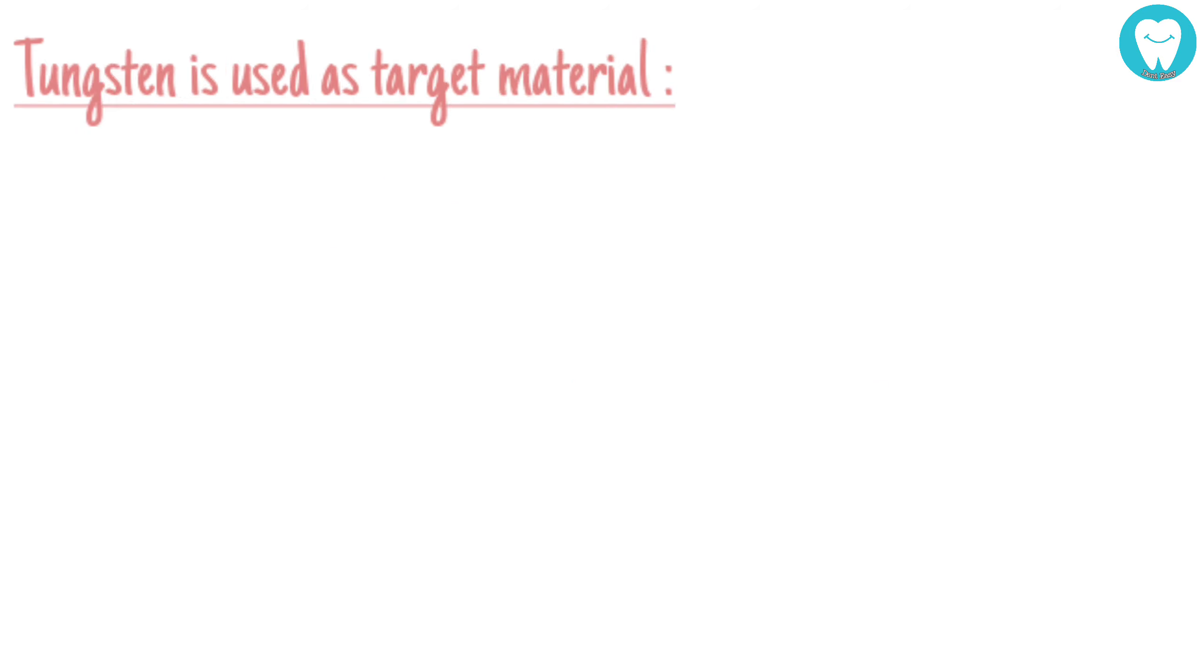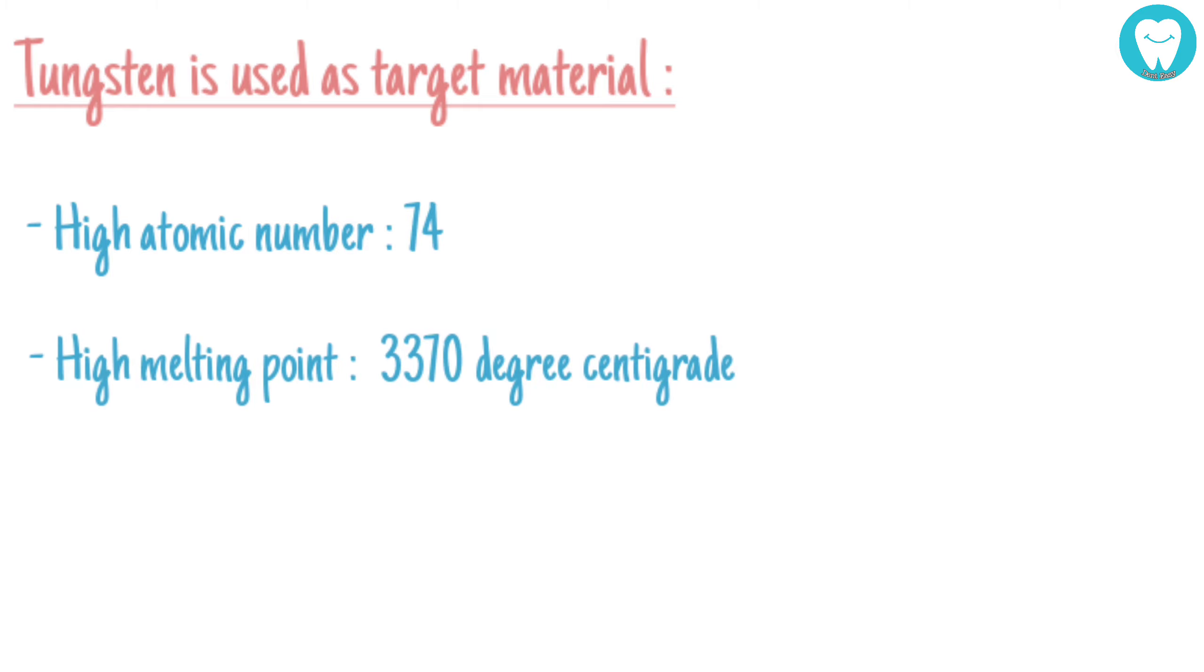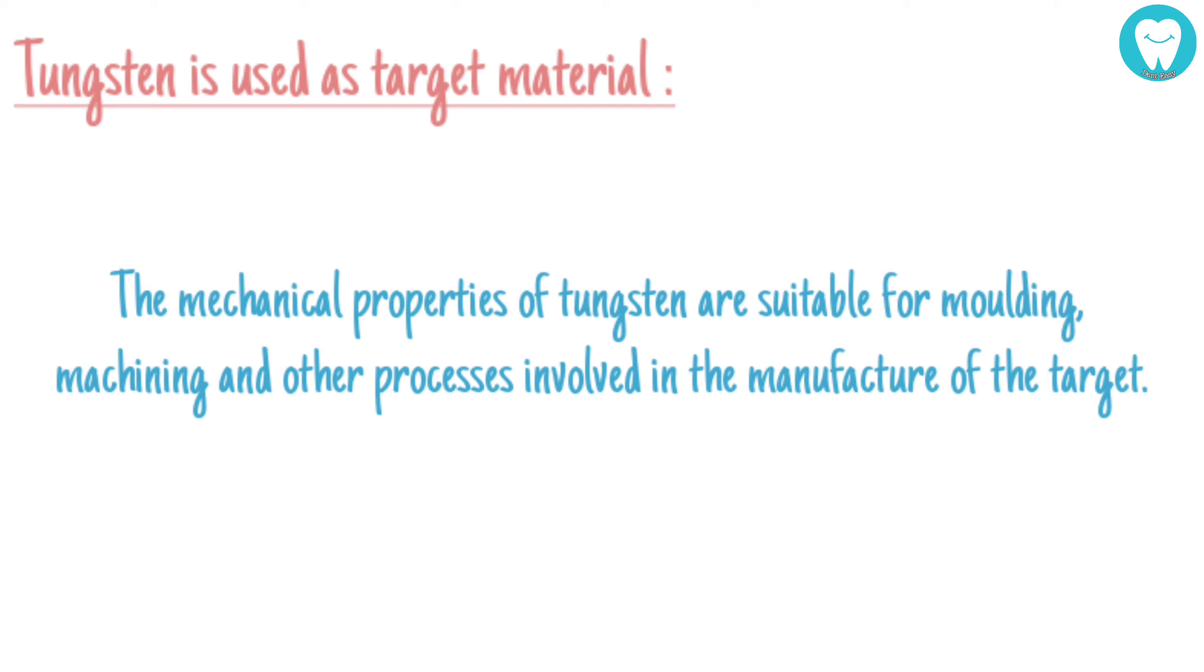Tungsten is used as target material as it has a high atomic number of 74, high melting point of 3370 degrees Celsius, and has low vapor pressure at high temperature. It does not have a high degree of thermal conductivity. This defect can be overcome by embedding a thin button in a copper stem to form the anode. The mechanical properties of tungsten are suitable for molding, machining, and other processes involved in the manufacture of the target.